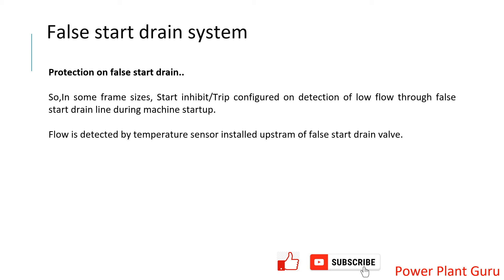Normally, the logic is different for different machines — when you have a false start, how much trip or inhibit time will be there varies. There are some machines where the false start drain valve must have a sensor to detect whether fuel or fluid is coming out. Advanced machines may have this kind of sensor, but it is not available in many machines. In those cases, the field operator and engineer has to physically judge and witness the compressed air and fuel coming out from those valves.